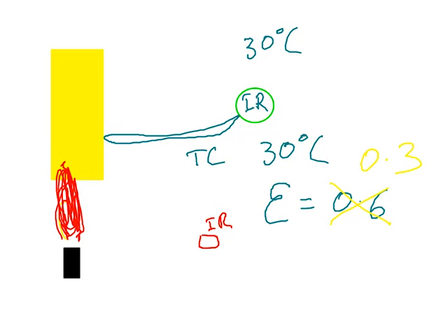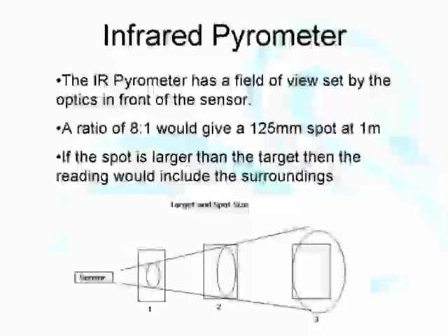They're good if you calibrate them for the one application you're going to look at. But when you move from one thing to another, they need to be recalibrated. Another thing to bear in mind is, if you're measuring something, then the sensor sees in a cone. So if you're measuring a switchboard, and that switchboard is 3 meters away from you, say, you're not just measuring the switchboard, you're measuring the switchboard and all of the wall around it. Whereas if you're only 1 meter away from that switchboard, you're measuring pretty well the switchboard. If you want to accurately measure that switchboard, you need to be pretty well right up against it, in which case you might as well use a thermocouple.